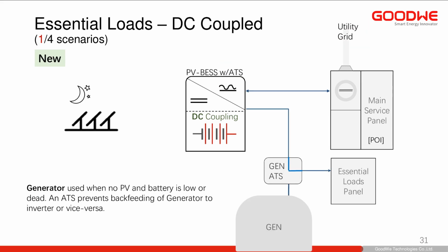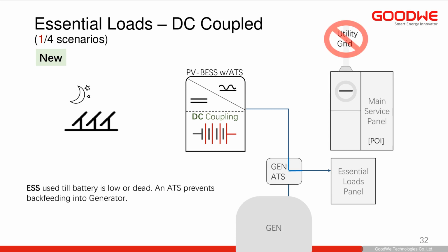In this next example, imagine there is a generator. Now the generator is connected to an ATS, but it is not connected to the backup circuit of the ESS. The ESS is your standby power source. So when the grid goes down, the ESS provides power to the essential loads panel, not the generator.